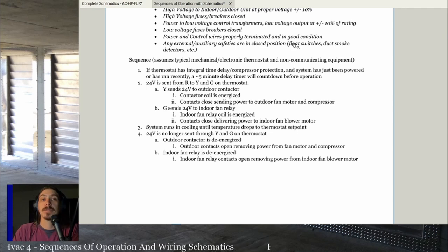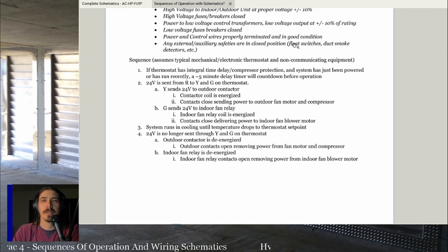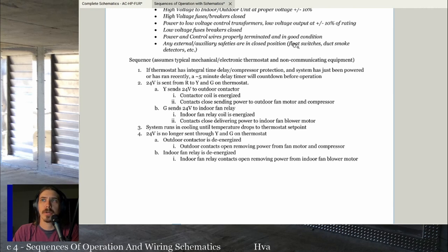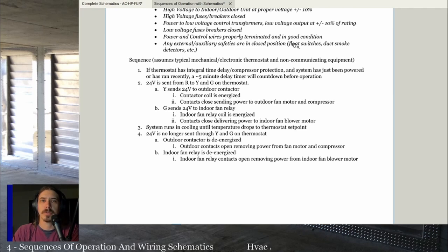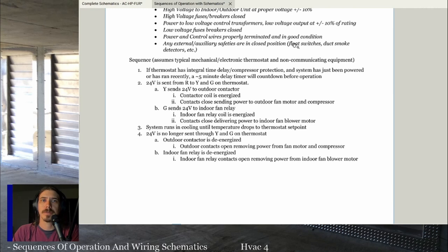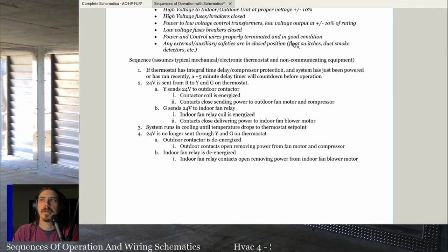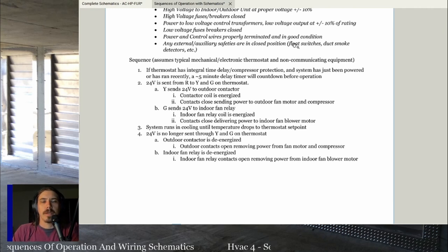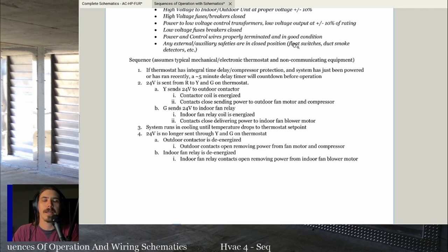Let's talk about a typical air conditioner sequence of operation. One thing to keep in mind is the sequence assumes a typical mechanical or electronic thermostat on non-communicating equipment — as simple as it gets, just straight AC, most likely a residential split system. The thermostat has an integral time delay or compressor protection. When the system has just been powered on or recently powered, you'll have a five-minute delay timer — it could be three, it could be five — that counts down before anything operates.